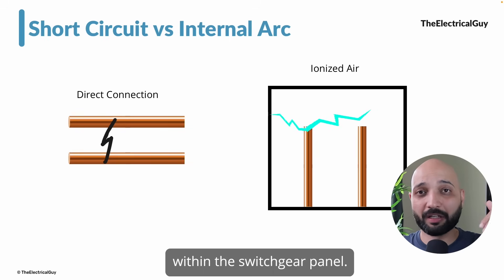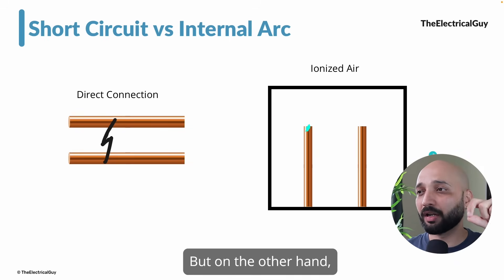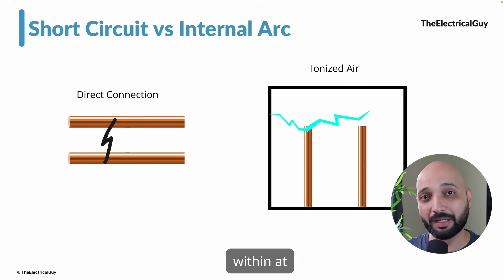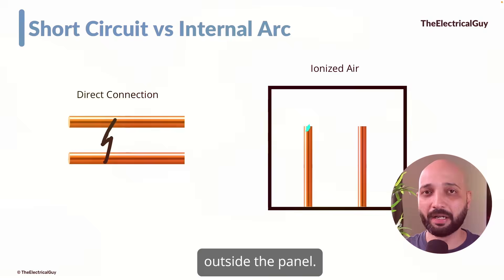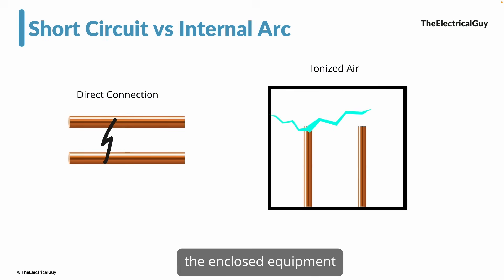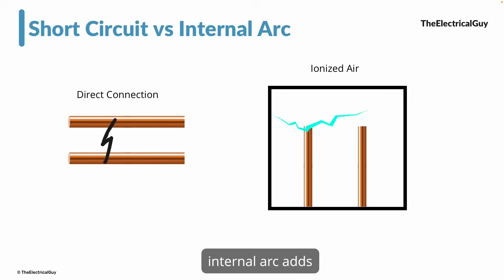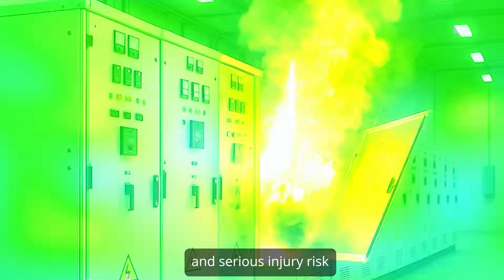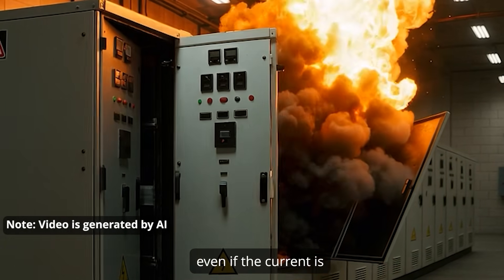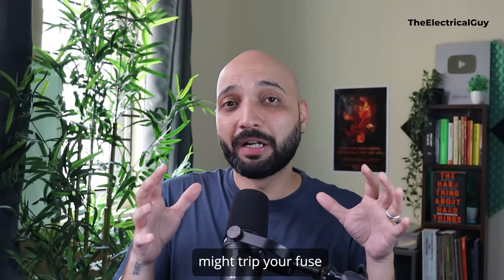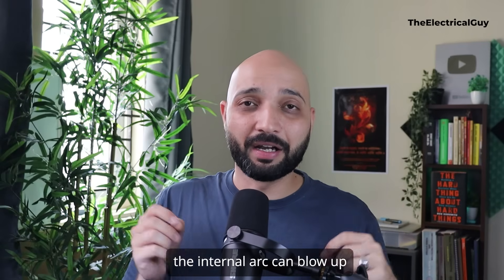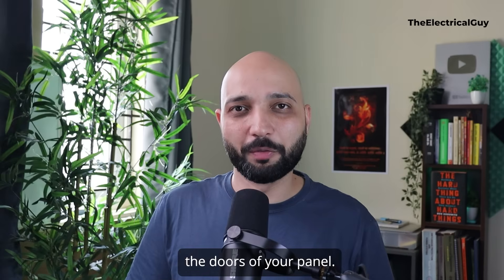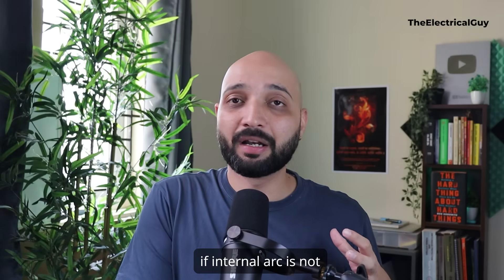A short circuit is not limited to inside the switchgear panel — it can happen outside as well. But internal arc is limited within the switchgear panel, happening only inside enclosed equipment where heat and pressure have nowhere to go. While both faults involve high current, internal arc adds two extra dangers: intense heat and mechanical pressure. The result is explosions, fires, and serious injury risk even if the current is interrupted quickly. To sum up, a short circuit might trip your fuse or breaker, but an internal arc can blow up the doors of your panel.